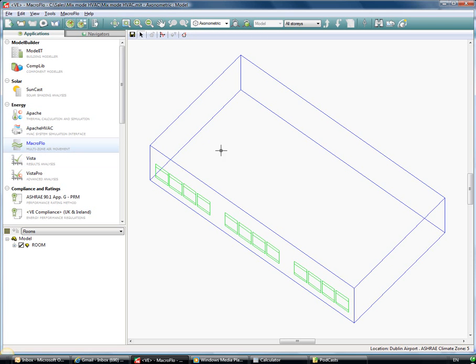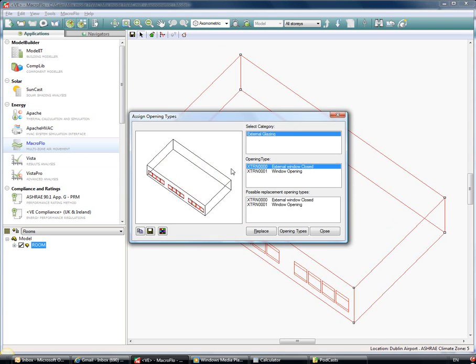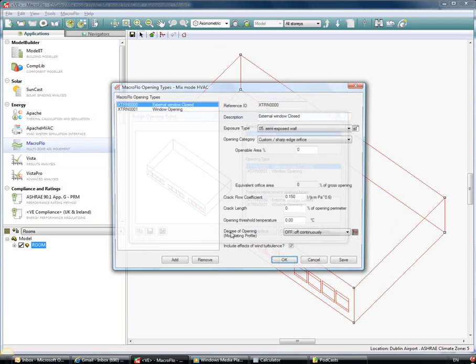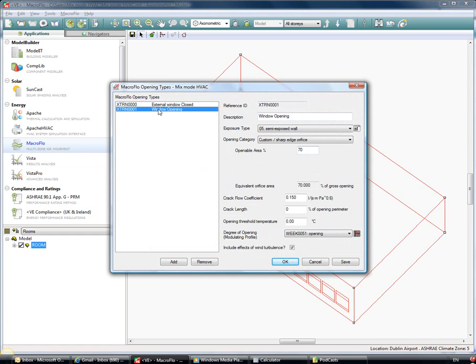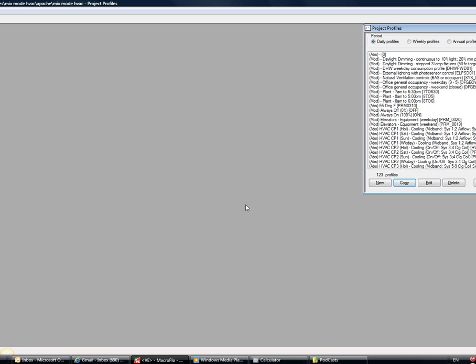As I look at this model I can move into MacroFlo and see what I've set up. When I look in MacroFlo I can see that I have a number of opening types created. I have an external window which is closed, so you can see it's closed, there's no openable area and it's off continuously. And I have a window opening which is 70% openable and has an opening profile.